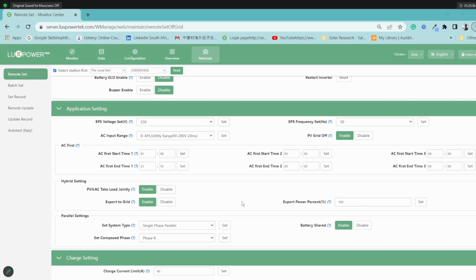Sometimes my memory is great. So what we've experienced is the default setting for the AC input range is set to APL, which has a low voltage range of 90 volts and a high voltage range of 280 volts. Now it says 20 milliseconds changeover time, which, let's say if AC trips or switches back on, it will use this over here.